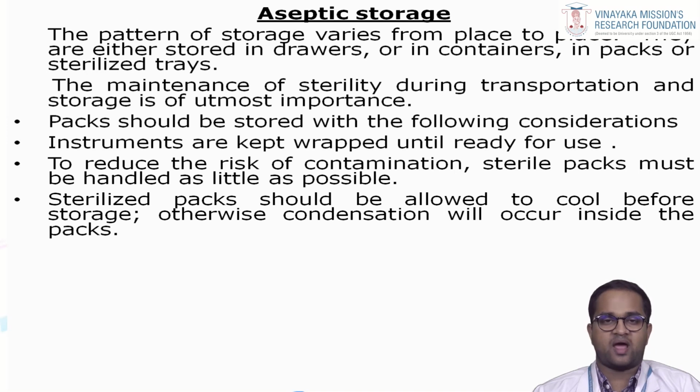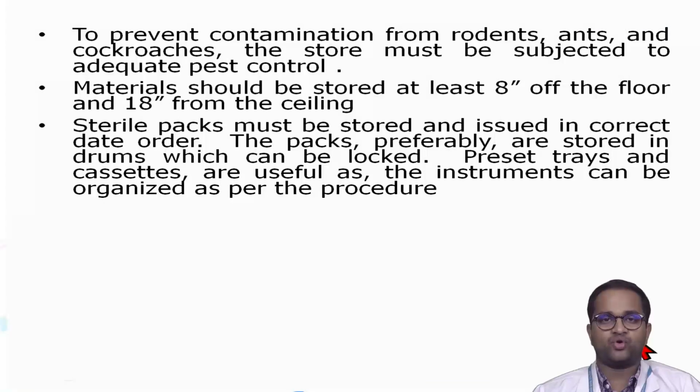The instruments are wrapped until ready for use. To reduce the risk of contamination, the sterile packs must be handled as little as possible. The packs should be allowed to cool before storage, otherwise condensation will occur inside the packages. To prevent contamination from rodents, ants and cockroaches, the storage area must be subjected to adequate pest control.